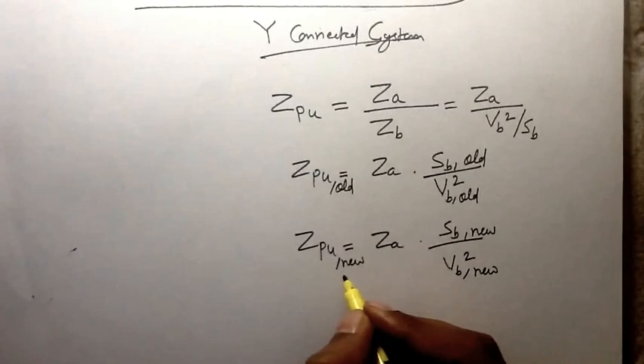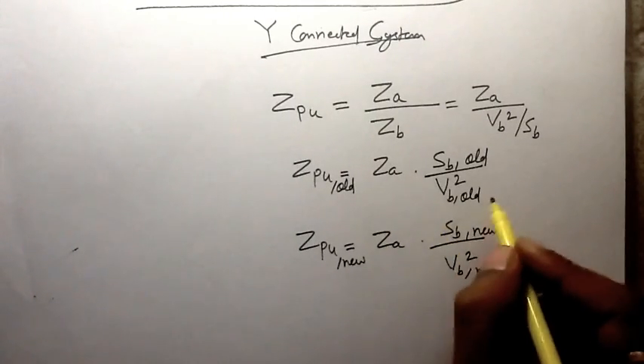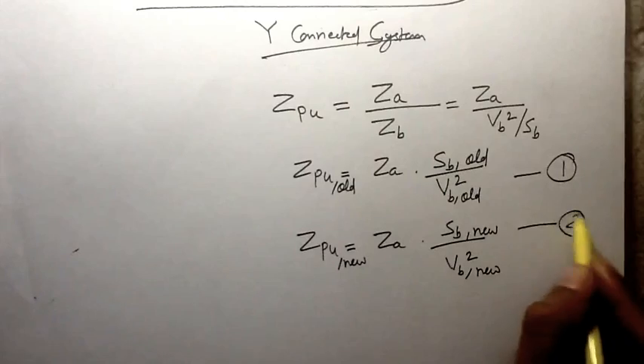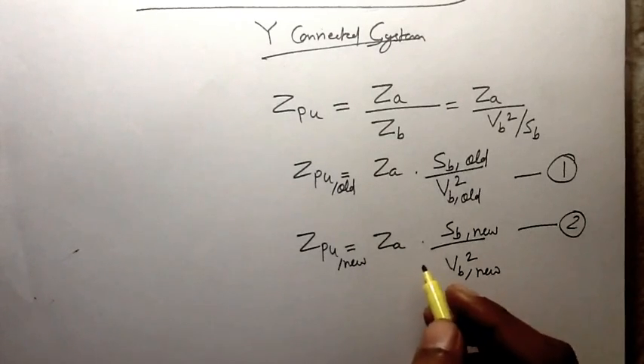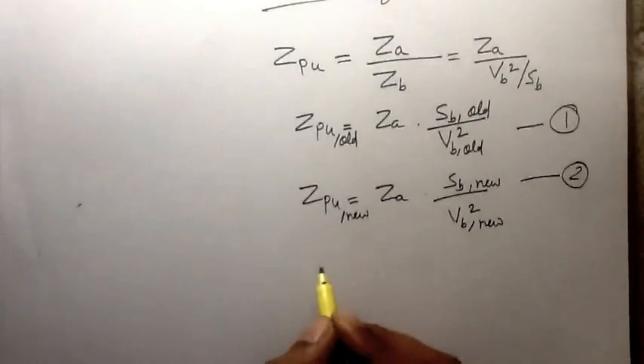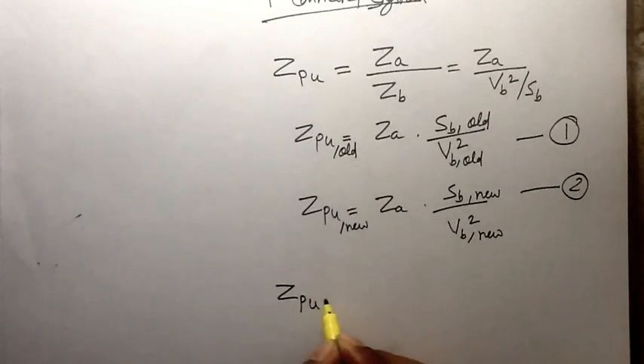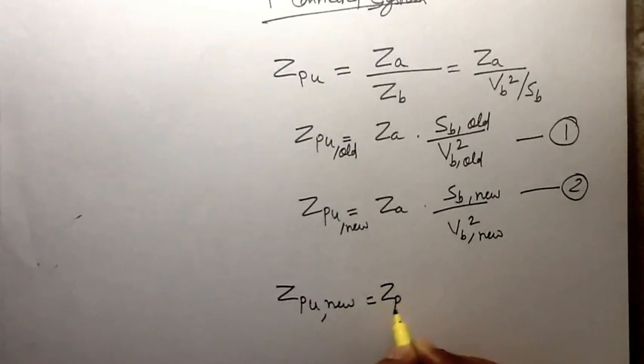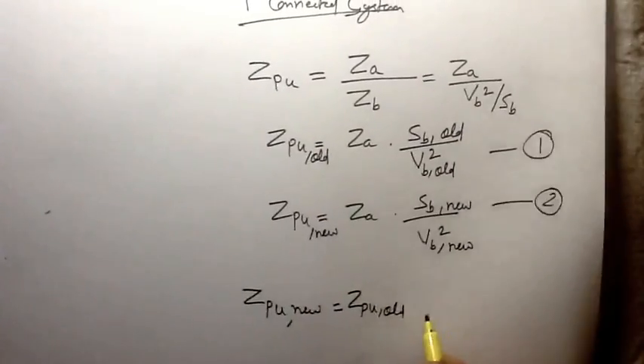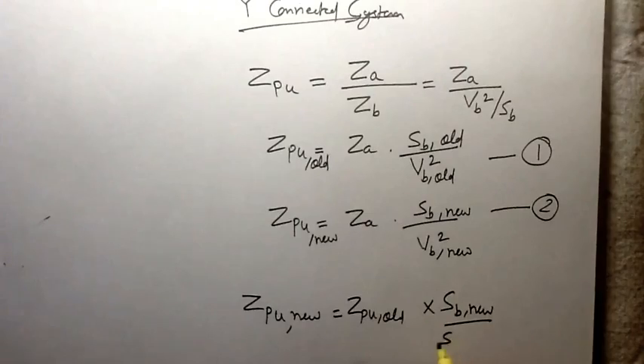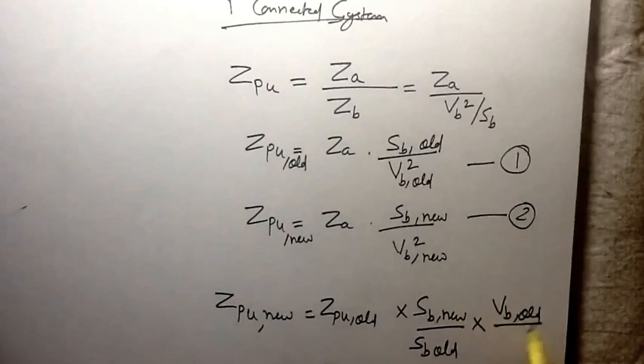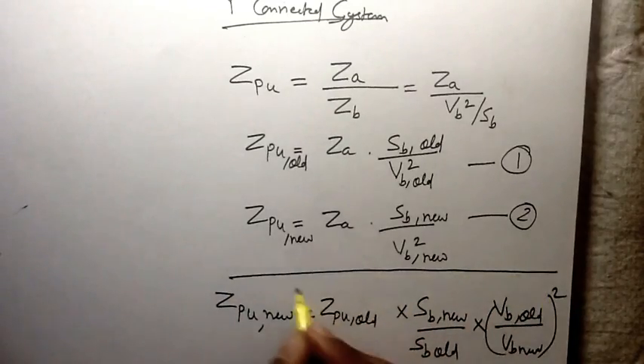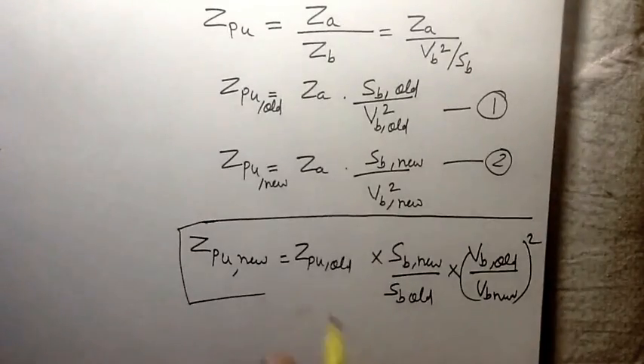Dividing these two equations — equation one and equation two — we arrive at the very important formula: Z_per-unit_new equals Z_per-unit_old times (S_base_new / S_base_old) times (V_base_old / V_base_new) squared. This formula is very important in power system analysis.